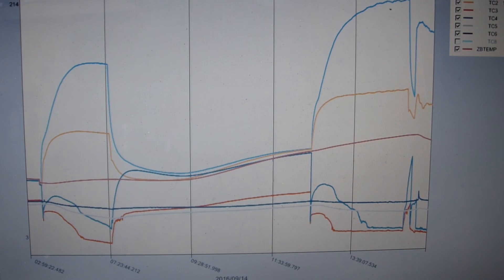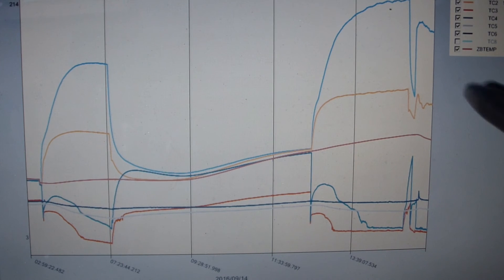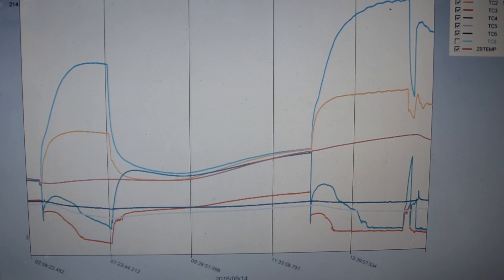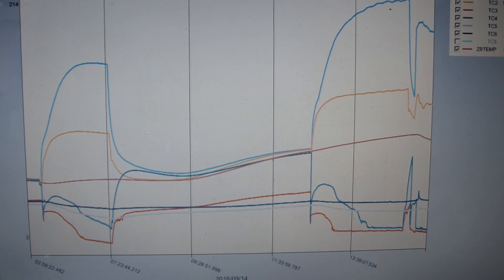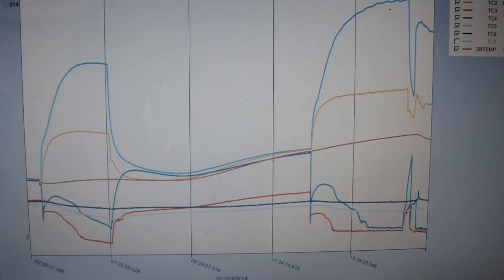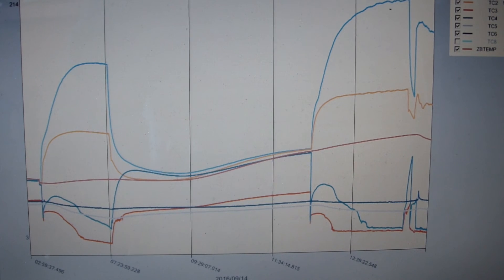I added a little bit of refrigerant which caused a little bit to back up in the condenser and again lowering the temperature on the subcooling end of things. There's a little bit more liquid backing up in there to discharge this heat before it heads onto the metering device. Then there's a small little blue spike there where I open up the door to check the situation on the glycol.